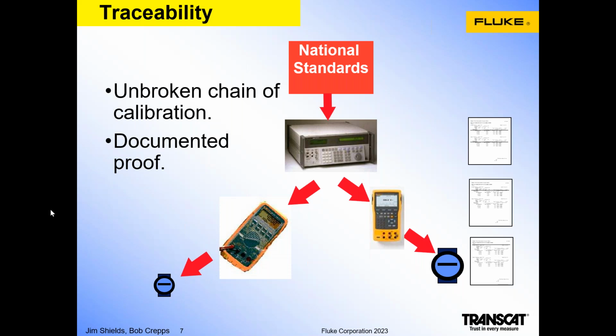So in this example, if you look at the very top of the standard, the national standards calibrates a bench calibration standard, for example, and that bench calibration standard has a document that covers its calibration. On that calibration documentation would be the serial number of the device, its calibration information before it was adjusted and after adjustment if it was required, the date and the time, who performed the work, and that document then documents the performance of the bench calibrator.